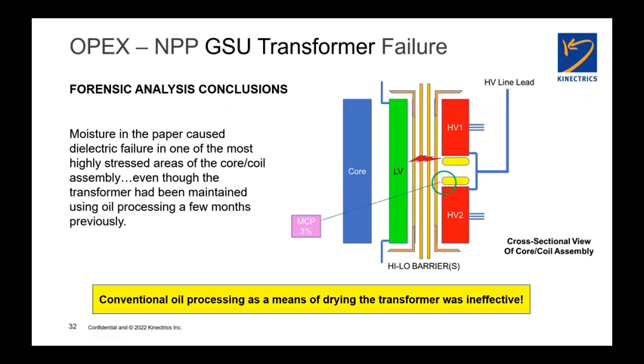To go back in summary here to the failure at the beginning, and with everything that we've talked about, this is a cross-sectional drawing of that single phase generator step-up transformer. We now know where the moisture is going to be the highest: in the coolest part of the core coil assembly. In this particular case, this was a directed oil flow pumped unit, 230 kV, so it had 7 wraps in the high-low barrier. These wraps are not near the conductor of either the LV or the HV, which are heat producing sources. So this has high velocity oil going through it. As I already mentioned before, the oil was at 42 degrees centigrade. And so this is the coolest part.